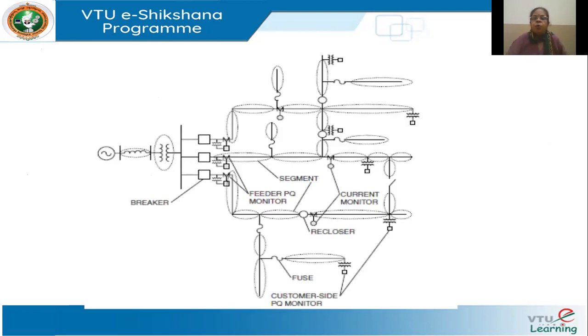So look at this figure. Here we have a number of monitors. This is a feeder. This is a substation, so we have different breakers. And this is a feeder. I have placed some current monitors at some locations in the feeders. Then the feeder PQ monitoring is there at the entrance of each feeder. And some customers have a PQ monitor. This is just random, just to give you the idea. There is some monitoring equipment at some of the customers' premises, not all of them. So you see, I am not placing a monitor throughout the network. I am placing it at some points. Then I divide it into segments, all shown by these circles.